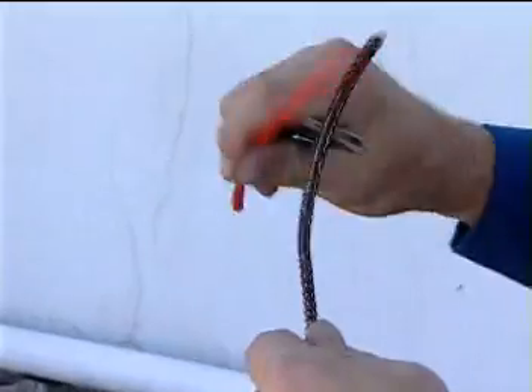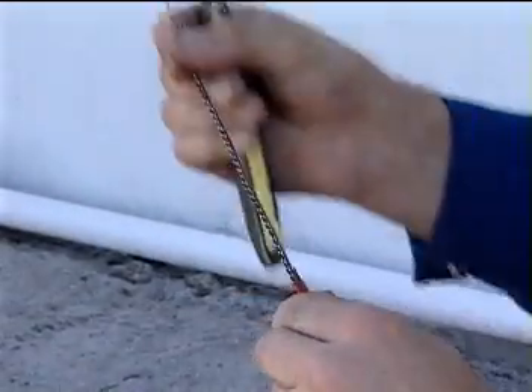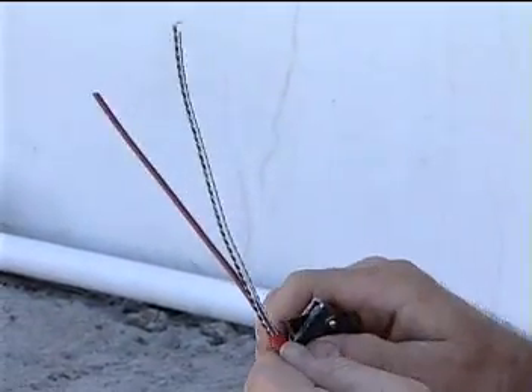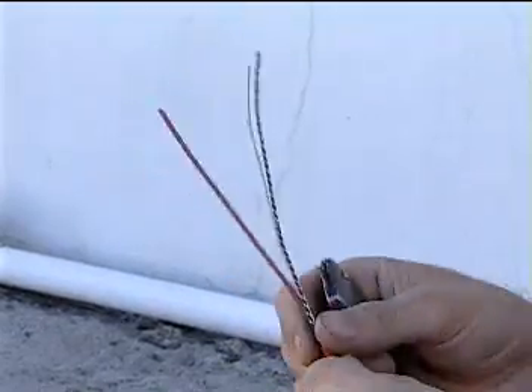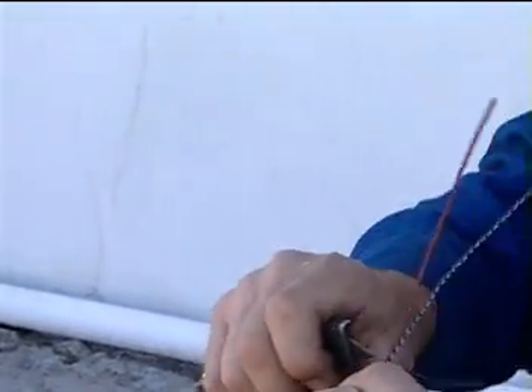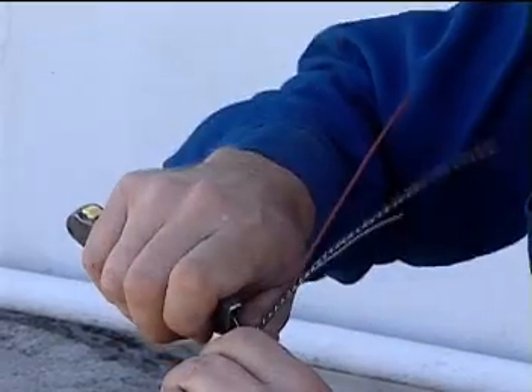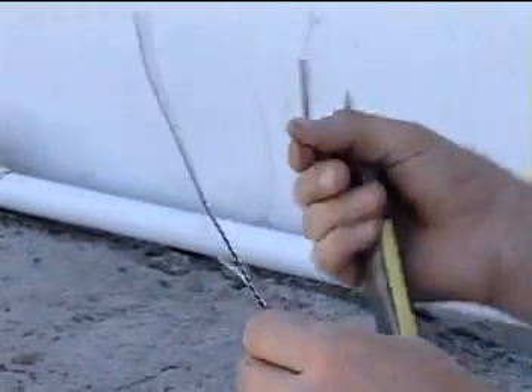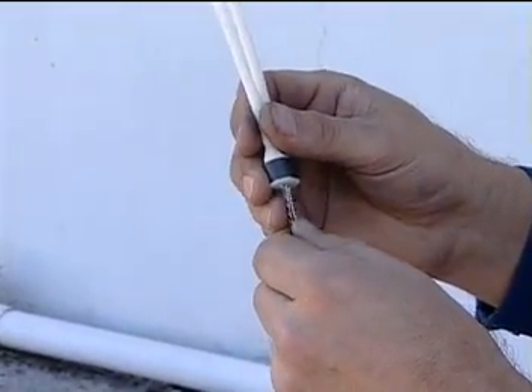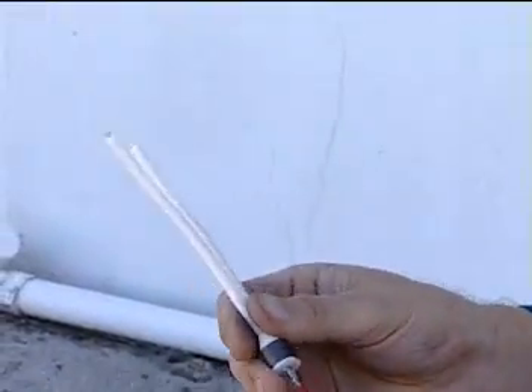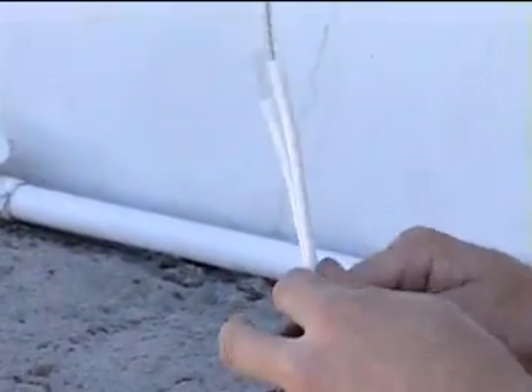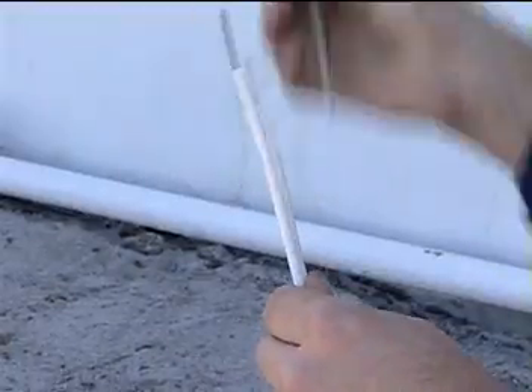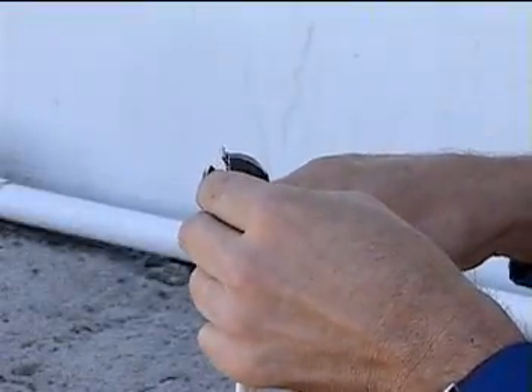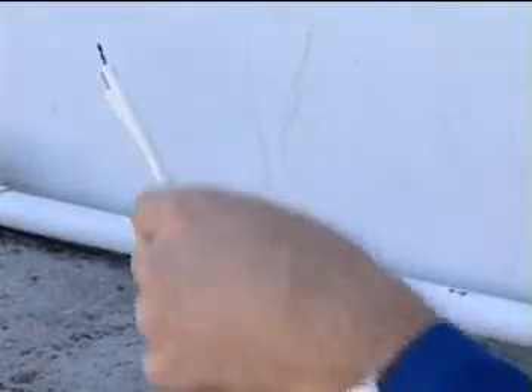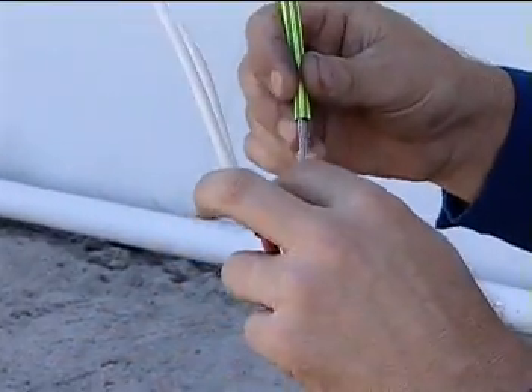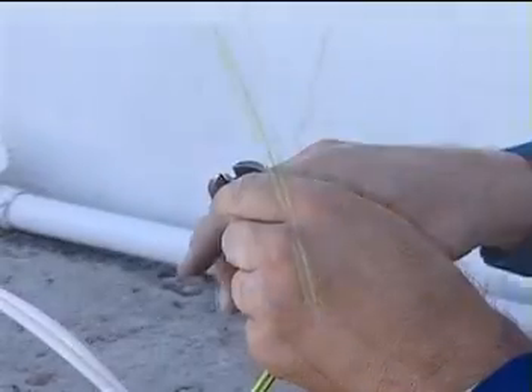Cut away the inner jacket. Then remove the exposed black fibers of the heating element, cutting them flush with the inner jacket. Next, remove the spacer from between the bus wires and trim it even with the jacket. Insert the bus wires into the guide tubes, making sure to seat the core seal onto the cable and remove the guide tubes. Cut the bus wires to the appropriate length. Slide the green and yellow tube over the braid and then trim the braid.